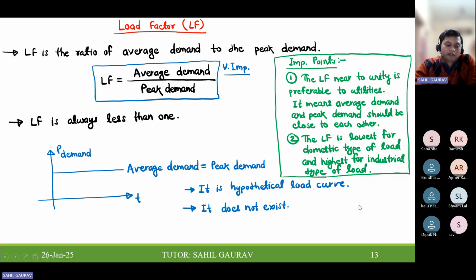Now let us see this last part where we will see the load factor. Load factor is the ratio of average demand to peak demand, and it is very important - remember this expression. It is always less than 1 because average demand cannot be greater than peak demand.